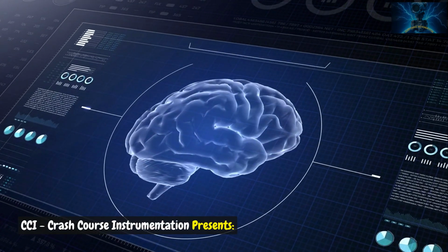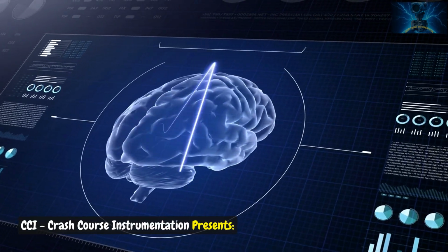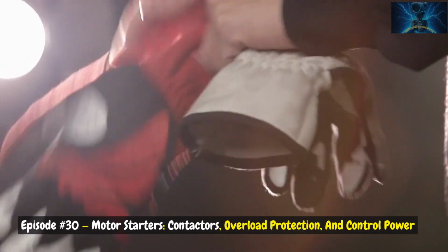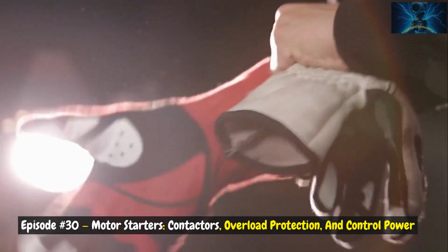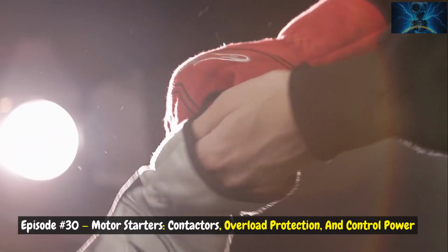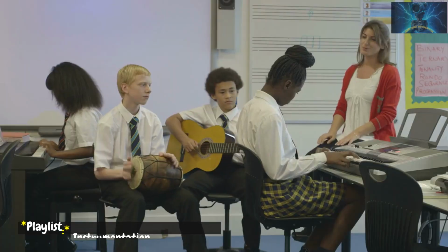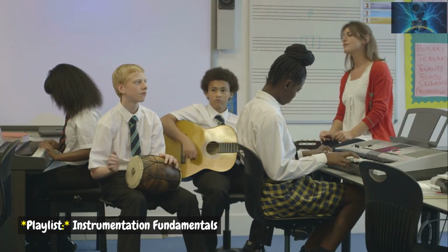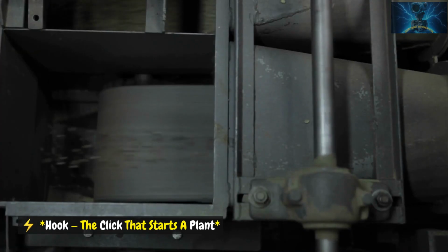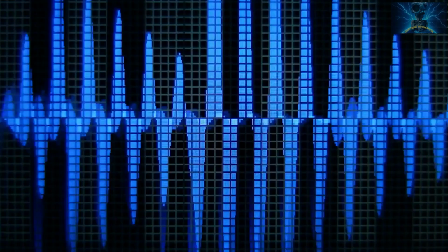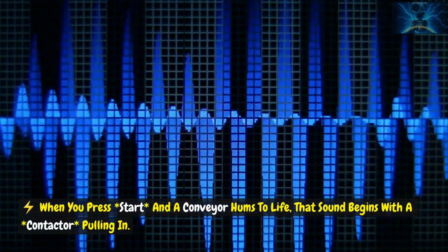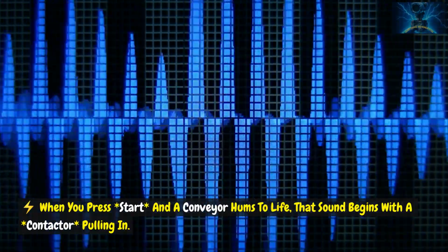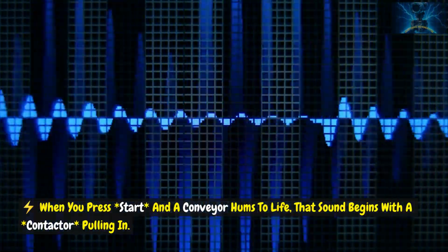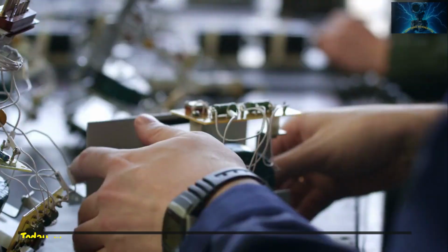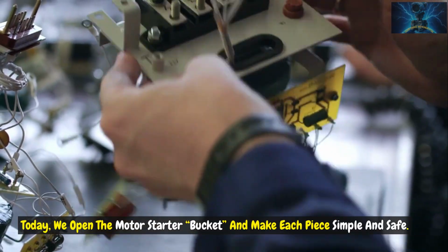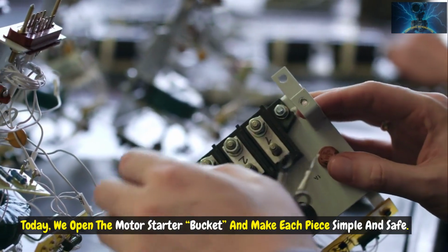CCI, Crash Course Instrumentation, presents episode 30: Motor Starters, Contactors, Overload Protection and Control Power. Playlist: Instrumentation Fundamentals. Hook: the click that starts a plant. When you press Start and a conveyor hums to life, that sound begins with a contactor pulling in. Today, we open the motor starter bucket and make each piece simple and safe.